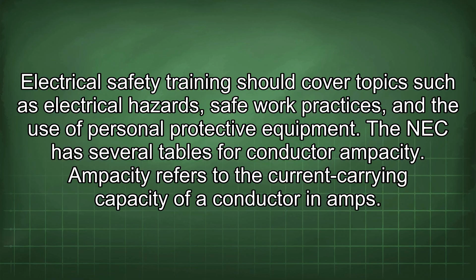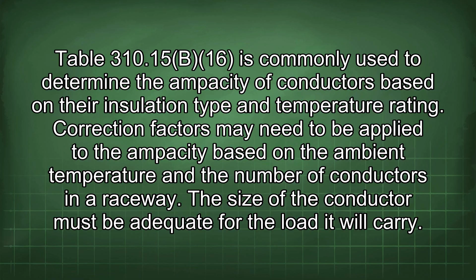Correction factors may need to be applied to the ampacity based on the ambient temperature and the number of conductors in a raceway. The size of the conductor must be adequate for the load it will carry. Undersized conductors can overheat and cause a fire.